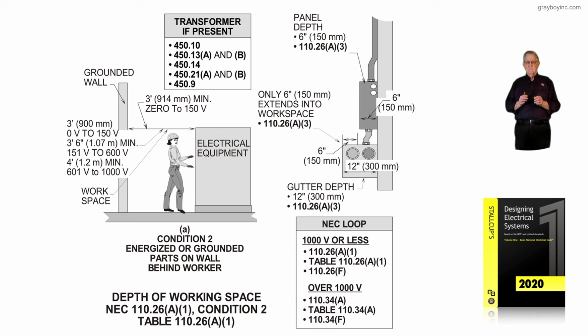But as a little summary now of Figure 5-2, the depth of the working space in accordance with 110.26(A)(1), Condition 1, and also using Table 110.26(A)(1), conditions are based upon the voltage and what is behind the worker's back while they are working and servicing that equipment. Now, be sure as the designer, installer, or inspector that we fully understand this. Now, I'm not saying you don't, I'm just saying make sure that we're on the same page here about Condition 1, and now we're going to move on into Condition 2 with the next illustration.